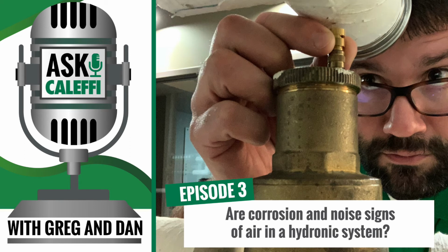They want that as a purge point, most of the time for purging debris. Some guys will use it even to purge a little air off if the system is completely empty. But honestly, those larger units, they're not using that to purge air. We have a skimmer valve about a third of the way down from the top, and that's going to be your purge point for removing air.